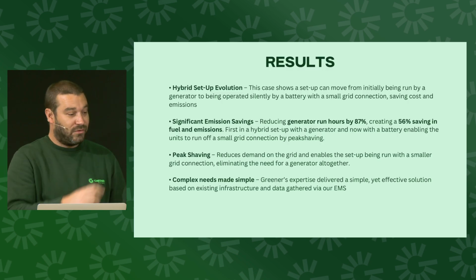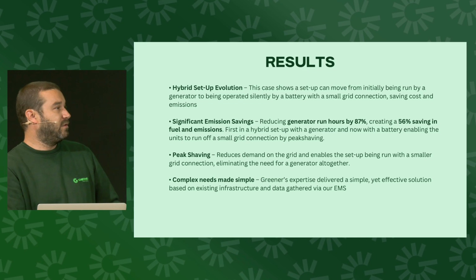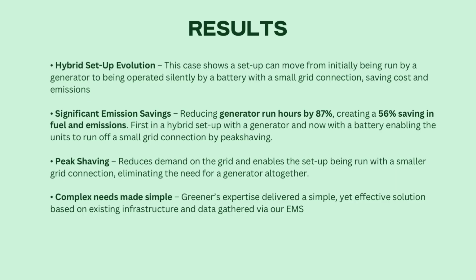So really the results were that we started with the hybrid solution, gathered the data, and from the initial setup, just by hybridizing the generator, still leaving the generator as the charging source for the battery, we reduced the generator run hours by 87%, which resulted in a 56% fuel reduction and obviously a related emission reduction on site. And then eventually we moved to the peak shaving setup, which eradicated the requirement for any diesel to be used on the site whatsoever. And every litre of diesel is what? £1.50 nowadays? Yeah, something like that. It changes.